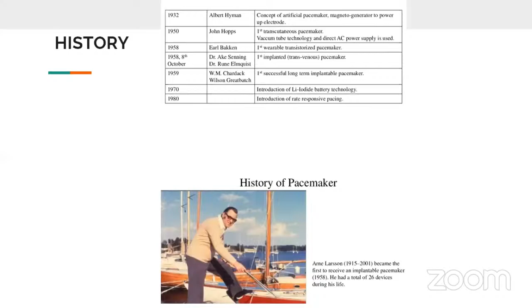Coming to the parts of the pacemaker, it consists of the power source, pulse generator, electrodes, timing control, sensing amplifier, and output driver. The pacemaker generator is a hermetically sealed device having the circuitry and the battery that determine the rate and strength of the electrical stimulus delivered to the heart. The power source is a lithium battery, whereas the sensing amplifier processes the electrical manifestation of naturally occurring heartbeats as sensed by the electrodes. The leads are insulated wires that deliver the electrical impulse from the generator to the heart and sense cardiac depolarization through the electrodes at the end, which touch the heart. The computer logic for the pacemaker and the output circuitry deliver the pacing impulse to the electrodes.